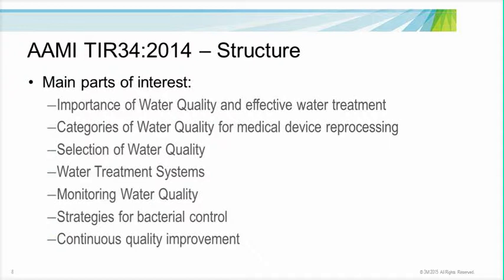The section on the categories of water quality for medical device reprocessing is designated with 2 categories of water quality, which we will cover in great detail later in this webinar. The part of the document on selection of water quality goes over all water quality requirements of cleaning, disinfection, and sterilization. The next section of the document, entitled Water Treatment Systems, includes designing a water quality system and general issues associated with the entire process.